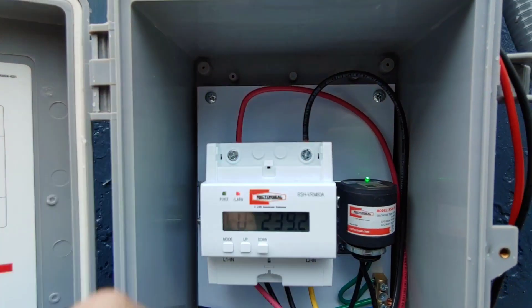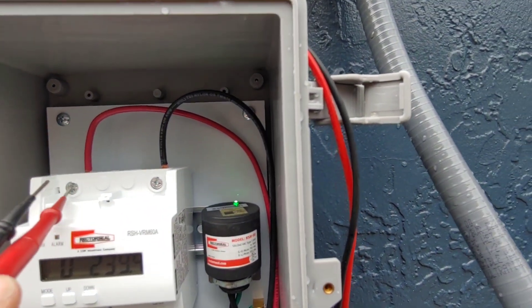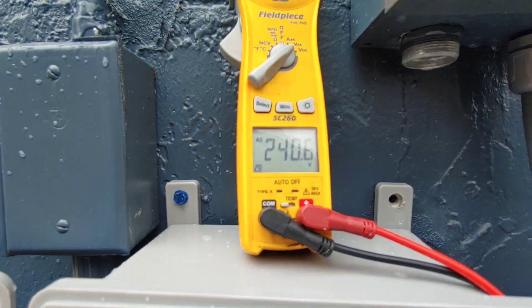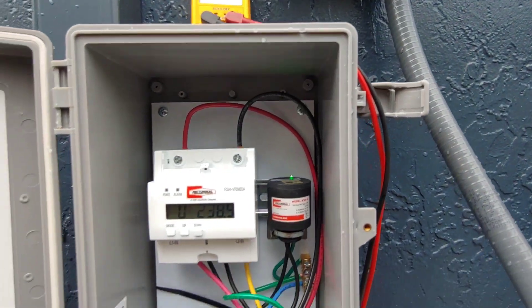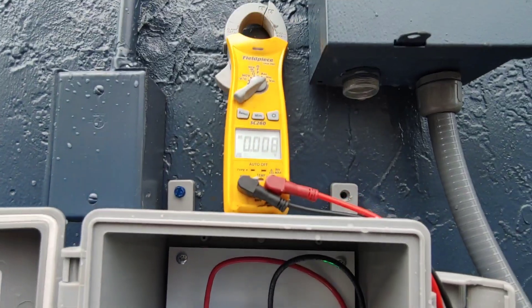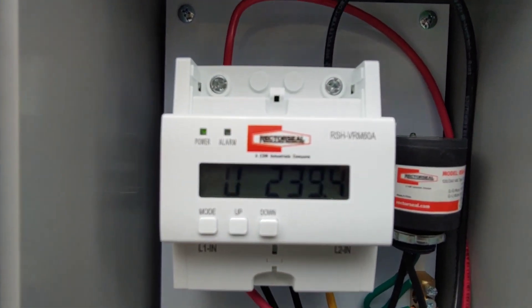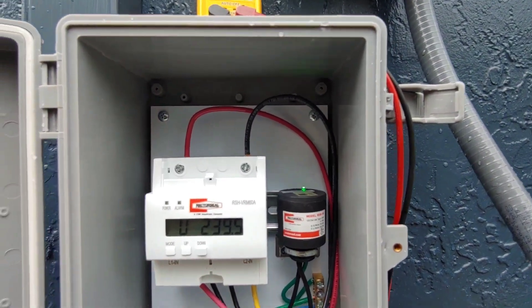I'm going to go ahead and check it against my meter — I have an older meter, so we'll see what the difference is. I'm getting 239 on the unit and 240 on my meter, so it's about a one-volt differential. It could be my Field Piece meter since it's been thrown around quite a bit and I don't think I've ever had it calibrated, so I'm assuming the unit's reading is correct.